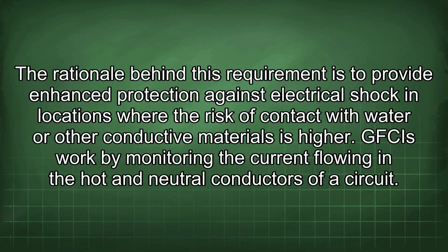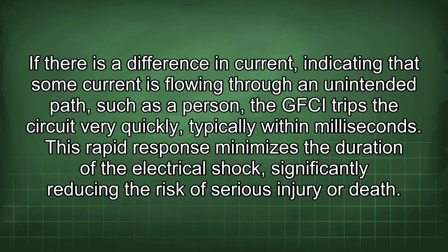The rationale behind this requirement is to provide enhanced protection against electrical shock in locations where the risk of contact with water or other conductive materials is higher. GFCIs work by monitoring the current flowing in the hot and neutral conductors of a circuit. If there is a difference in current, indicating that some current is flowing through an unintended path, such as a person, the GFCI trips the circuit very quickly, typically within milliseconds. This rapid response minimizes the duration of the electrical shock, significantly reducing the risk of serious injury or death.